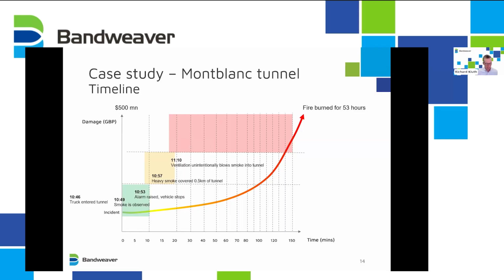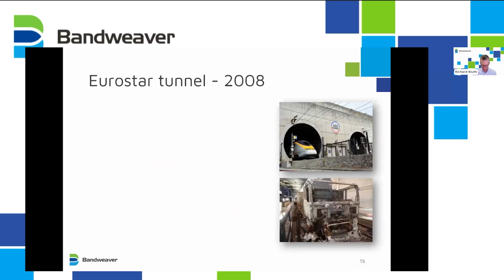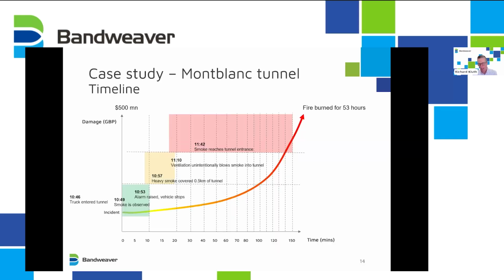causing fatalities. And this is one of the big improvements we've seen: our systems can connect with ventilation systems to prevent and manage the smoke in a way which can reduce the fire and not feed it and cause additional damage. So by half an hour, the smoke had reached the tunnel entrance. Long before this, the fire services really didn't have access to get into the tunnel, and then it burned for another 53 hours. So a really catastrophic event.